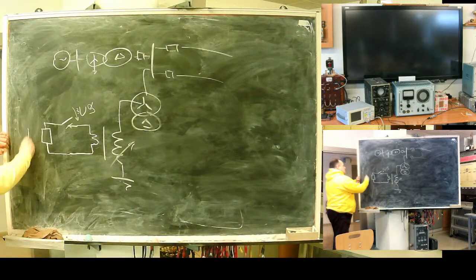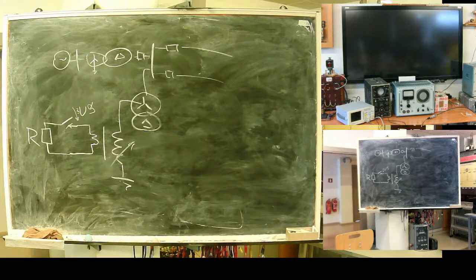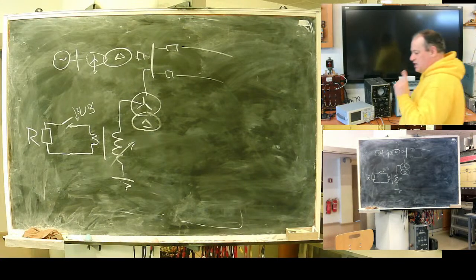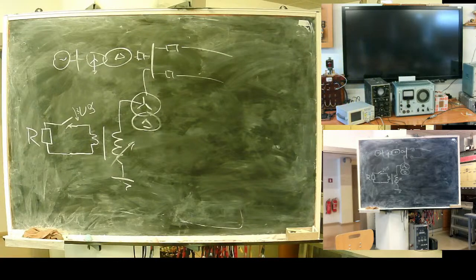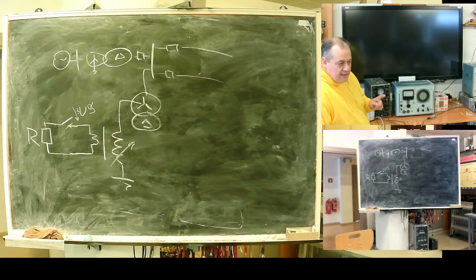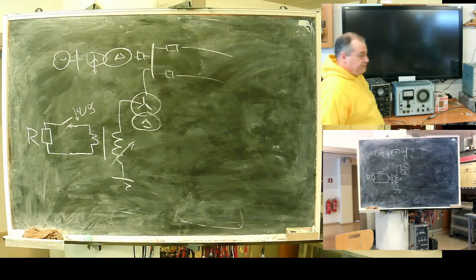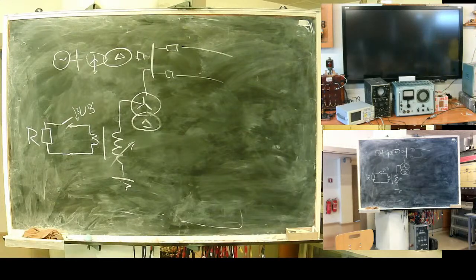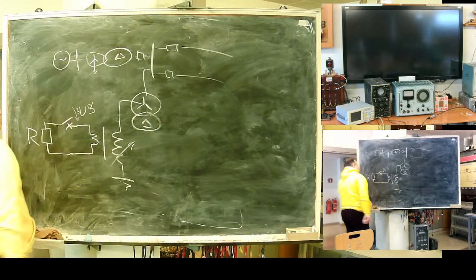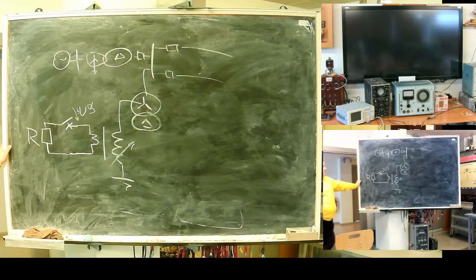This resistor, I'm warning you, remember this, cannot withstand fault current continuously. It can hold full current only within 5 seconds. Then it burns out. Do not operate such kind of coils without protection.